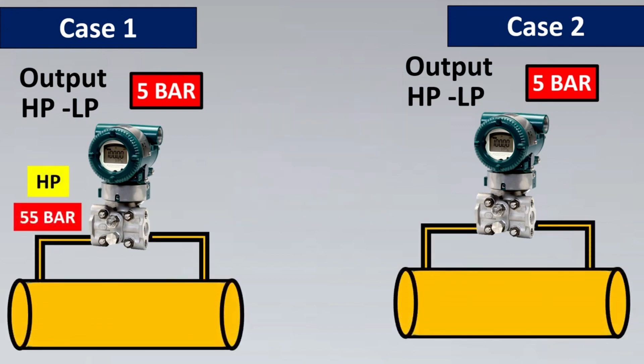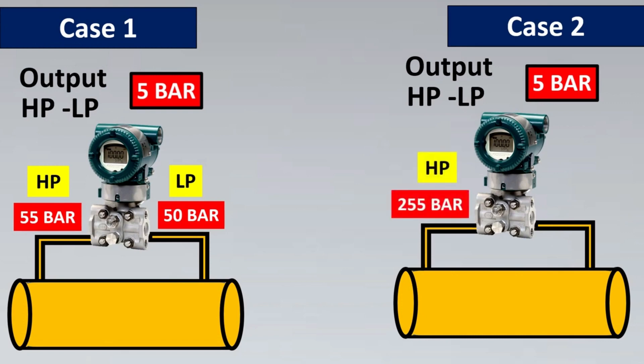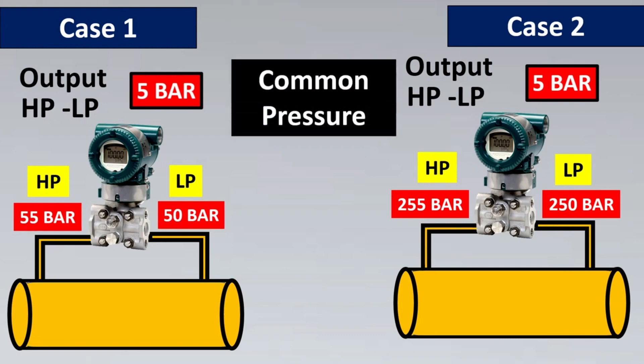For the first transmitter, the HP side is experiencing 55 bar and the LP side is experiencing 50 bar, so HP minus LP is 5 bar. For the second transmitter, the HP is experiencing 255 bar — which is pretty huge — and the LP side is experiencing 250 bar, so the output is again 5 bar. These both are not experiencing the same pressure.